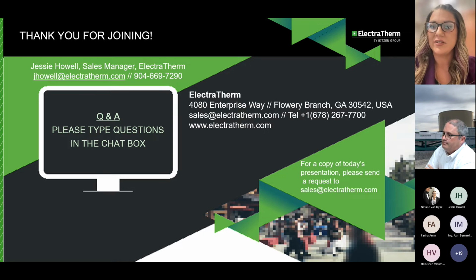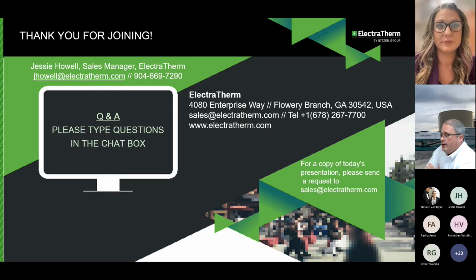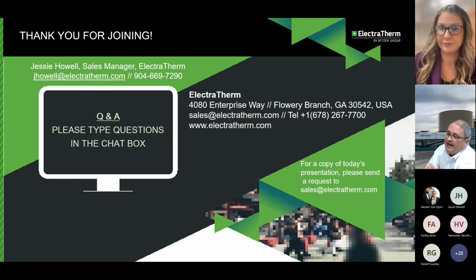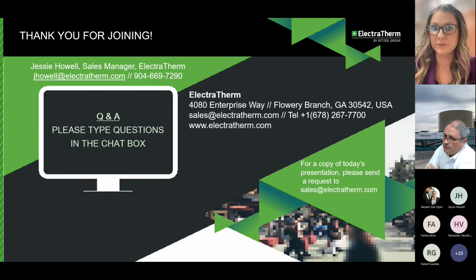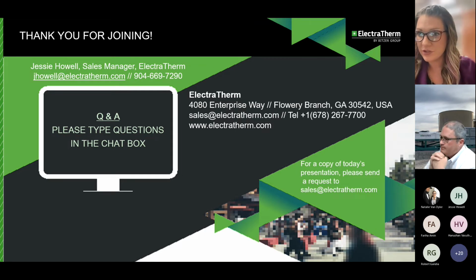That's great. All right, our next question is, how is my engine cooled if your generator goes down? Good question. We talked about the AC800 that you can see behind me and Jessica spoke to at length. If you leave the engine cooler in place in a brownfield or an existing site, and you attach ours, it basically gives you redundant cooling. So if your cooler already has a PTO driven cooler on it, it keeps on running. And if the ORC portion, the power generation, the box in front over here goes down, you still have a cooler behind it, and that keeps working and controls the temperature if you're using jacket water. So we really do believe you're adding to the redundancy and reliability of the site by actually adding the additional cooling that also generates power for it.